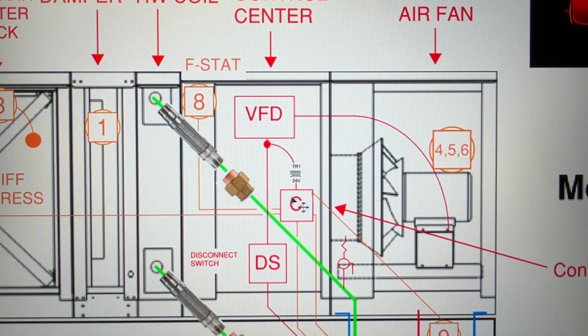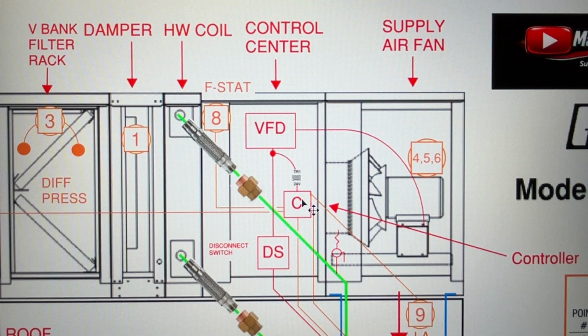Then we have down here the controller. So we take that 208 power and that goes to this VFD. This VFD will be the signal caller to the fan on what it needs to do and when. So when we send a control command, it will ramp up or down according to what we're telling it to do. So the internal control here, this controller takes all the data from the unit and brings it into one central place here where we can interact with it.